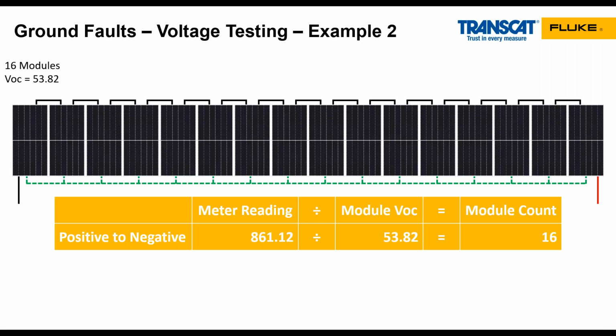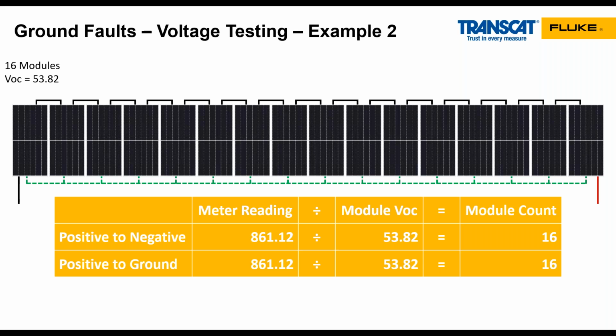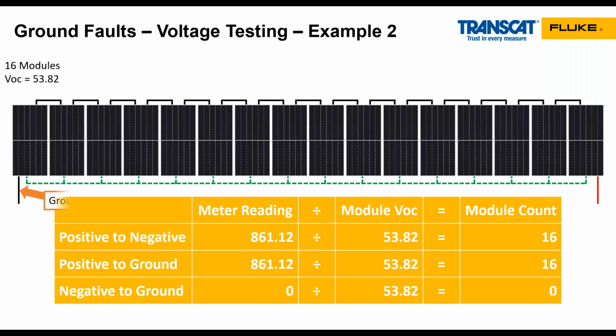Another example, quick, same set of modules. My positive to negative reading was the same, 861 volts. My positive to ground was also 861 volts. Divide that by 53 gives me 16 modules. My negative to ground was 0, which is what I expected. That means there are 16 modules between the positive and the ground fault, and 0 modules between the negative end and the ground fault, indicating that there is a ground fault on the negative home run wire between that last negative module in the string and wherever it goes to, either a combiner box or an inverter.